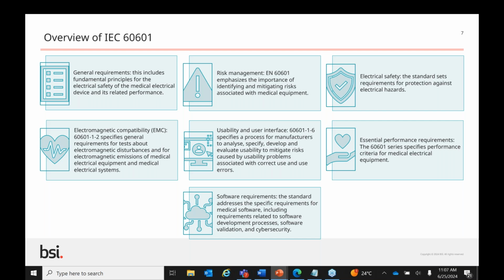There's EMC, and this specifies general requirements for tests relating to electromagnetic disturbance and emissions of medical equipment. It covers risk management, so this requires manufacturers to follow a risk management process through the life cycle and works in tandem with the risk management process to reduce risk and validate its implemented control. Usability and user interface: this defines a process for manufacturers to analyze, specify, develop, and also evaluate usability in order to mitigate risks from usability issues related to both correct use and use errors.